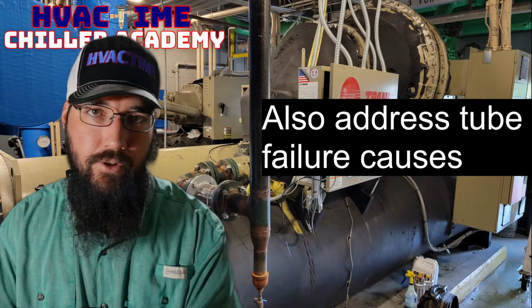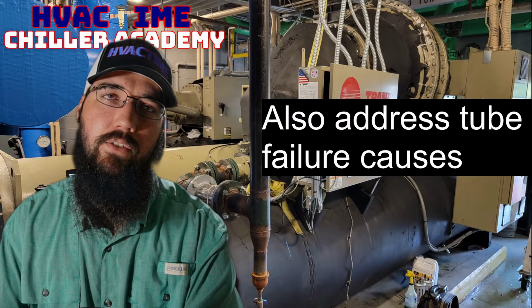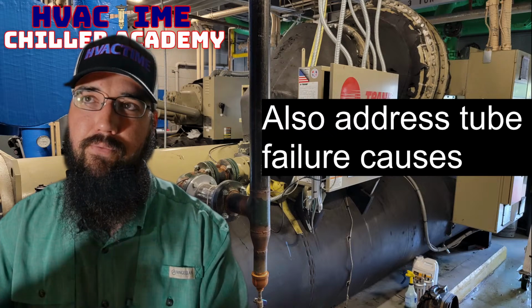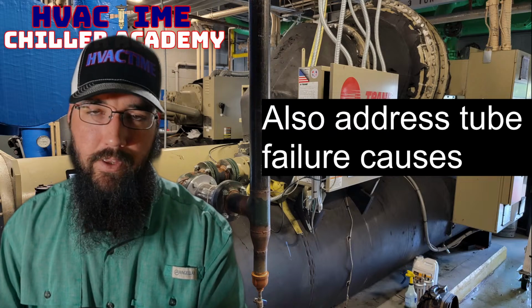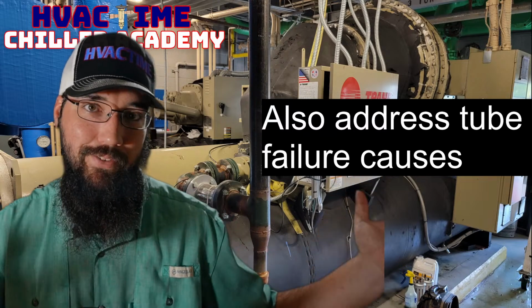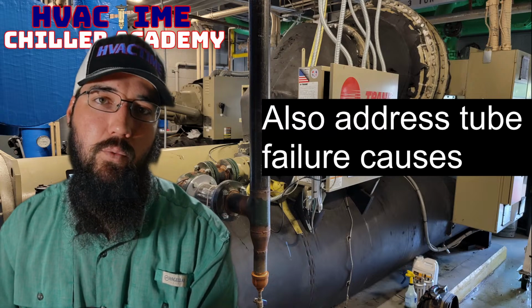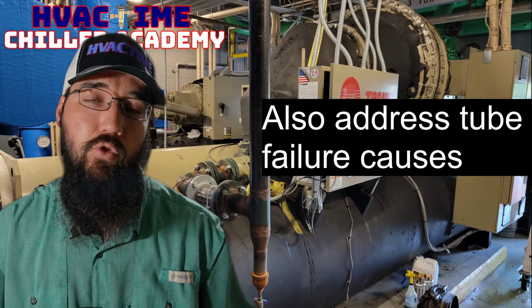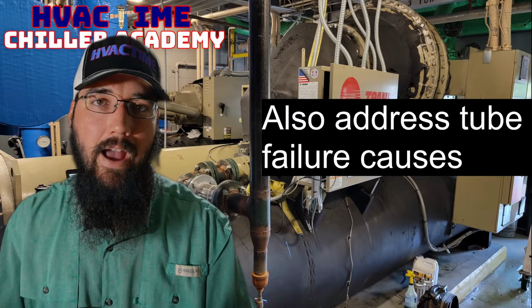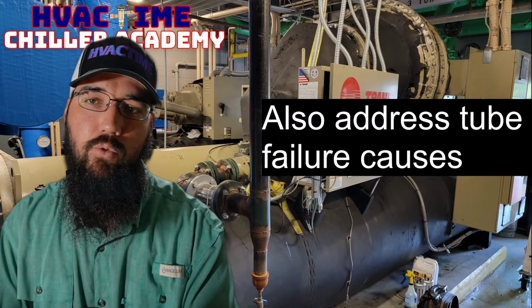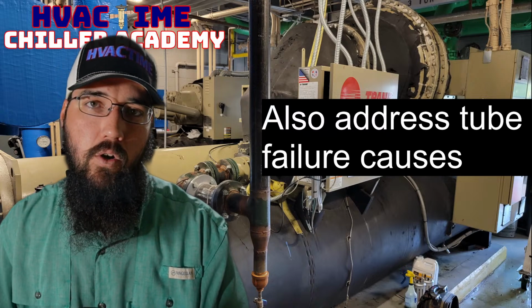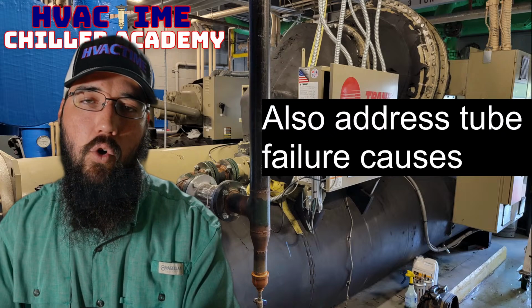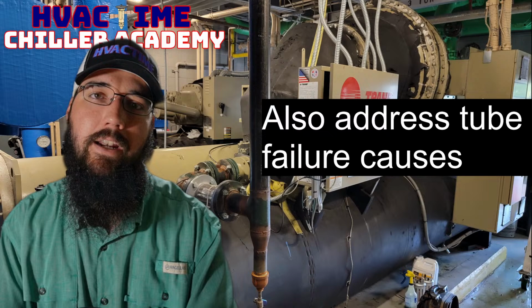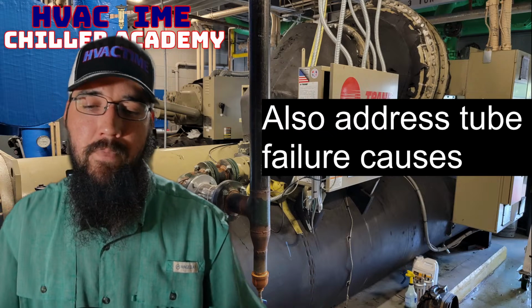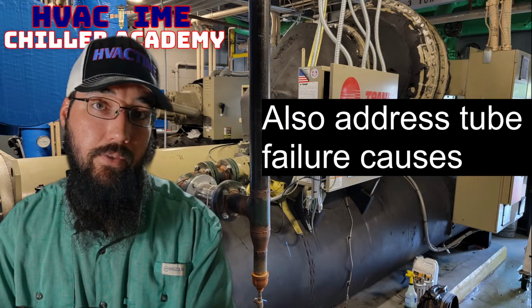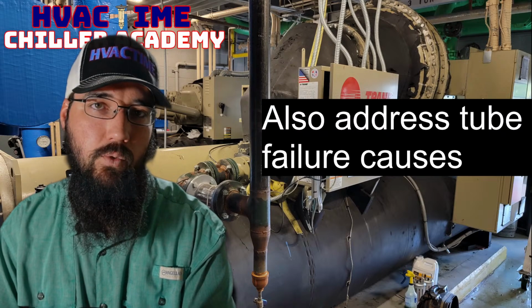You could have general erosion. If you've got a system with a lot of heavy debris flowing through it, whether that be mud, silt, whatever the case, other parts from the system, that can put a lot of extra wear on the tubing itself. It's also going to mean you're having to brush those tubes far more often, and brushing the tubes as an act creates more wear. As more wear is added, you thin the wall of the tube. Eventually the tube wall can get so thin that it can't hold up to the refrigerant pressure and the water pressure anymore, and a leak ends up forming.